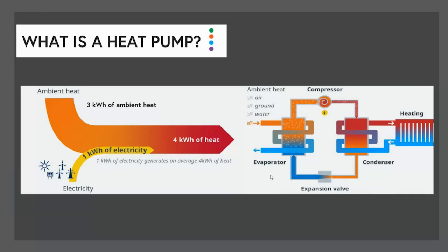You can see up in the top left corner of that image, it says ambient heat has got air, ground, and water. Now you may have heard that there are such things as air to water heat pumps, ground to water heat pumps or geothermal heat pumps, and water to water heat pumps. What that is, is different methods of transferring the energy to the system. We're going to be specifically focusing on air for this presentation, although there are other versions of heat pumps that get their energy differently, from the ground, using a ground loop, or from a water source like an aquifer or a stream or something like that. But we're going to talk about air.